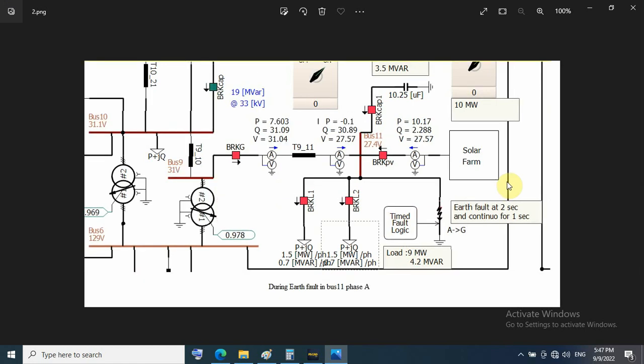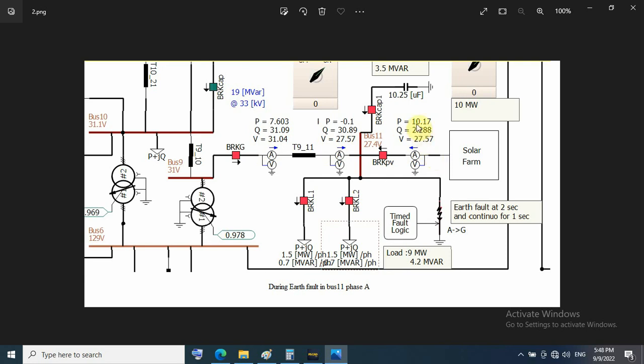Here, this photo is during earth fault on bus 11 phase A. The fault is inserted by time logic after two seconds from simulation time and continues for one second. During earth fault, the PV generates about 10 megawatt and 2.2 megavar, compared to before about 9.9 megawatt only and 0 megavar.